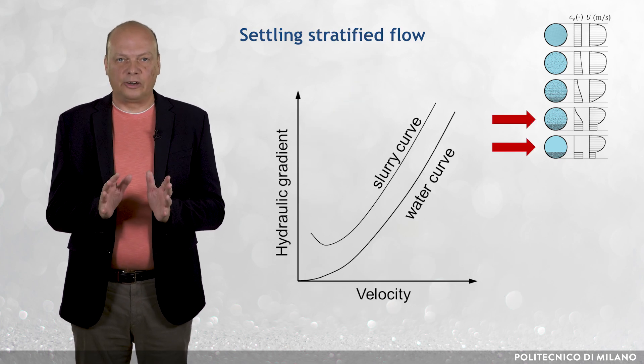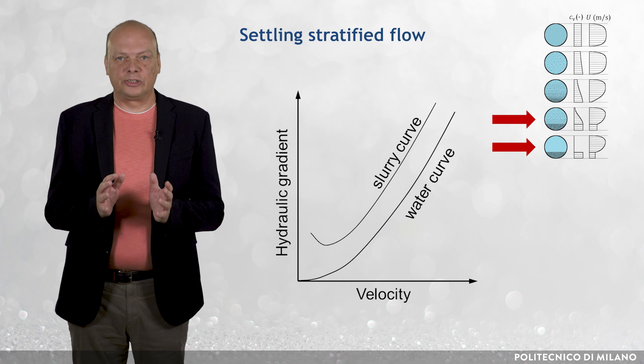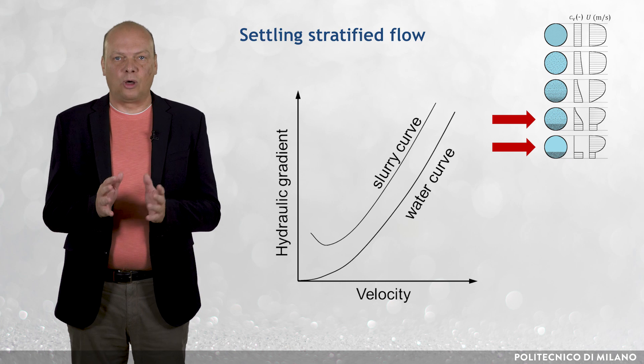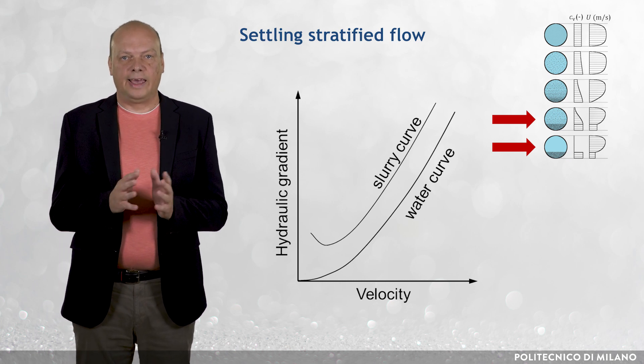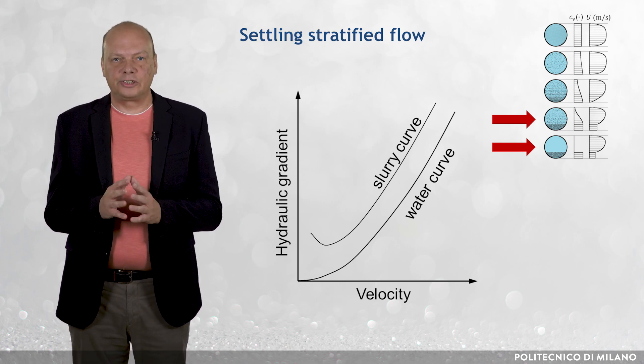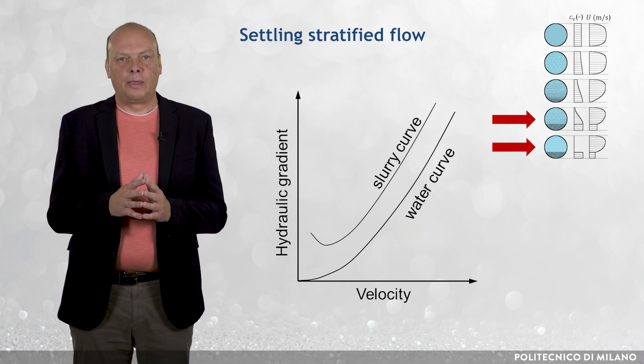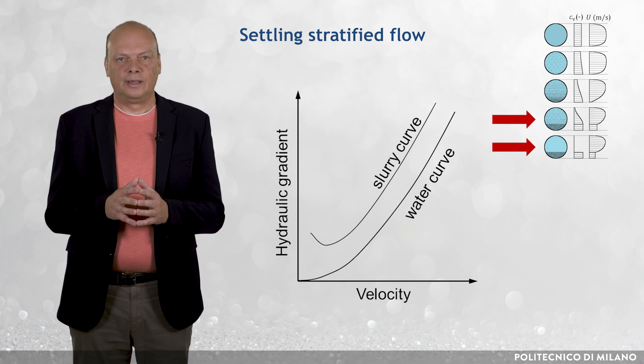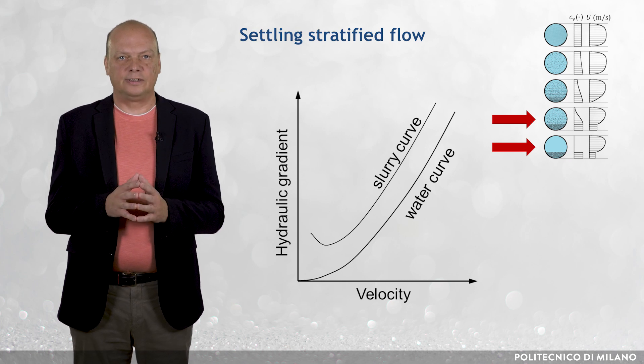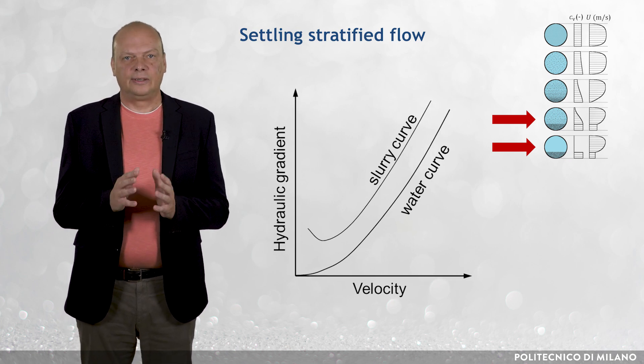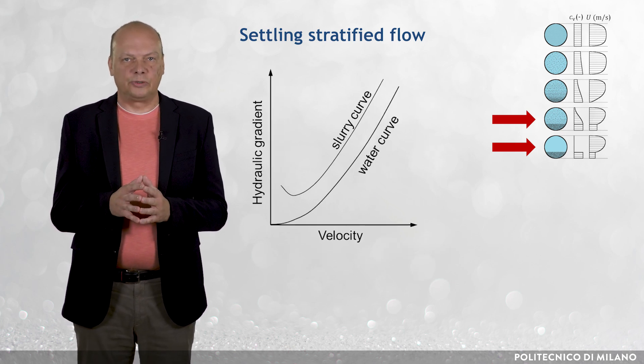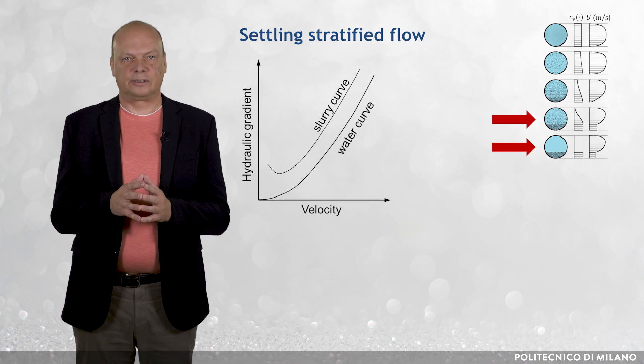If coarse particles are transported, then partially stratified flow or even fully stratified flow is the only plausible flow mode. Hence, contact friction is the dominating friction mechanism through which the transported solids contribute to the pressure gradient. The contact friction is weakly sensitive to flow velocity, and therefore the pipe characteristic curve of fully stratified flow virtually does not tend to the carrying liquid curve.